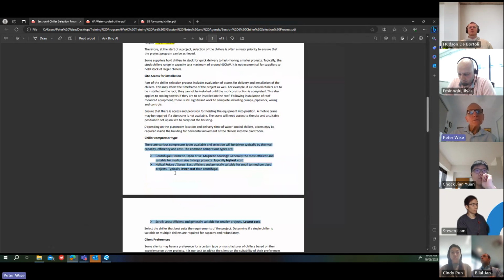And typically centrifugal chillers will be the highest cost. The next lower cost option, and it's a less efficient chiller, is the helical rotary or screw type machine. Less efficient, generally suitable for small to medium-sized projects. It can be air-cooled or water-cooled, and typically lower cost than centrifugal. So let's have a look at one of those.